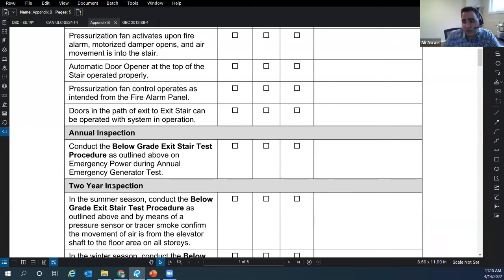So you got to make sure that it's on emergency generator, because this is an important piece of it that we want. And what we do for the initial test, we do it on emergency power as well, because that's your initial test. You got to consider the worst case. The worst case should be your initial test, to just make sure that the system is going to be working, and the worst case scenario is like everything is on emergency. And what we do, we run the whole test on emergency. It usually takes about 2 hours that it needs to be on emergency.